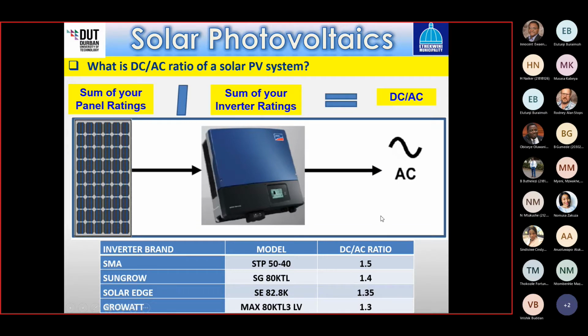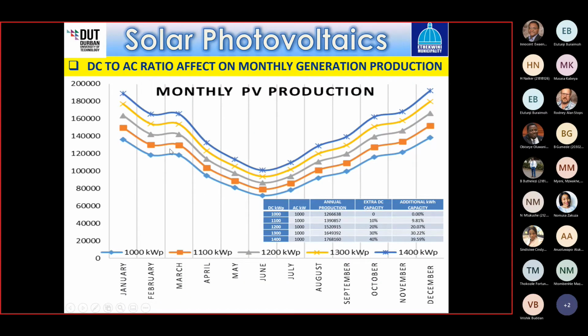So what would be the effect of increasing your DC to AC ratio as opposed to going 1-to-1, installing 1 megawatt of DC panels versus 1 megawatt of AC inverters? How will it affect production? We did a quick simulation study, and this is how it affects it. The different colors show that as we increase the DC, we kept the AC size at 1 megawatt, and we increased the DC size from 1 megawatt to 1.1, 1.2, 1.3 and 1.4 megawatts. We stopped at 1.4 because the inverter had a DC to AC ratio of 1.4, so we didn't exceed it.